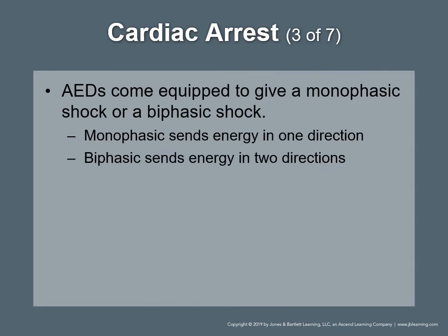Fully automated AEDs deliver the shock automatically. There are few fully automated AEDs left. AEDs also come equipped to give a monophasic shock or a biphasic shock. Monophasic sends the energy in one direction from negative to positive. Biphasic sends the energy in two directions.